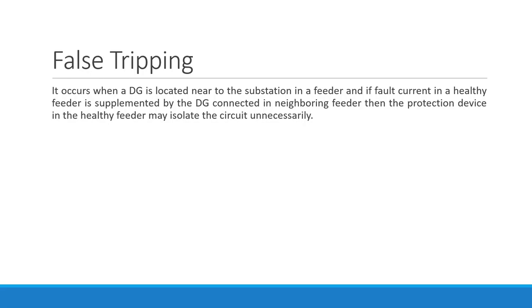False tripping. It occurs when a DG is located near the substation in a feeder and the fault current in a healthy feeder is supplemented by the DG connected in a neighboring feeder. Then the protection device in the healthy feeder may isolate the circuit unnecessarily. So false tripping is possible because of the location of the DG, you could say.